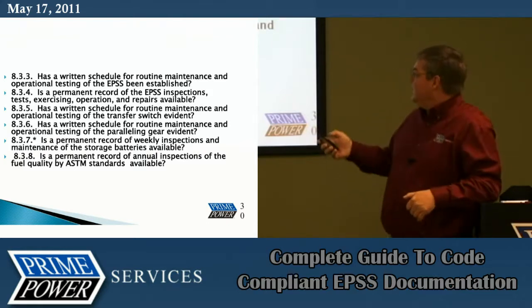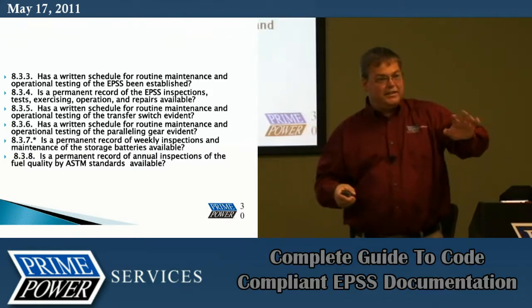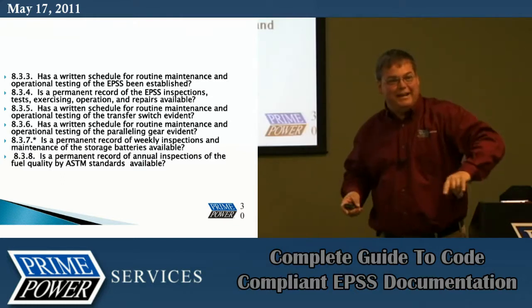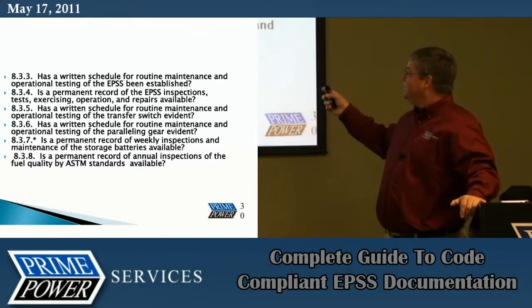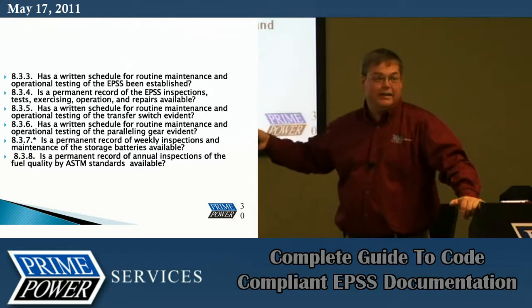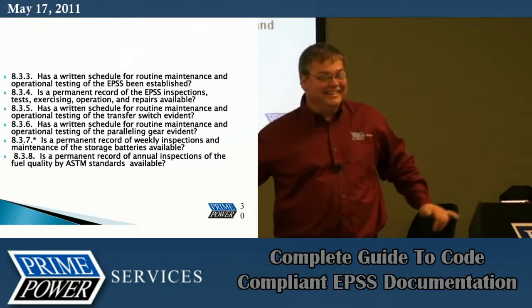Now, some interpretation comes into play here. Does this mean a visual inspection, or do you have to run a test on it? You have to run a test. You need to check that battery with whatever means you have of testing.